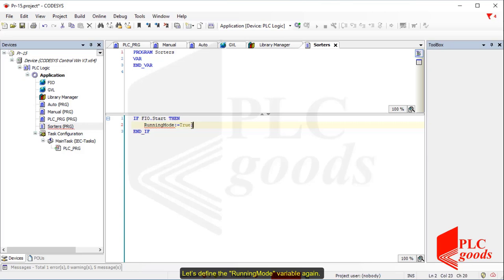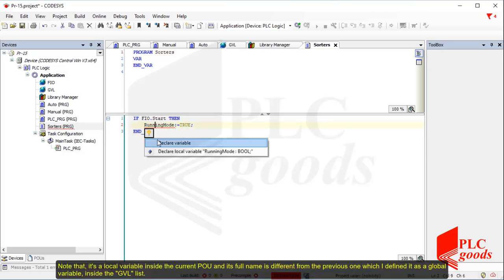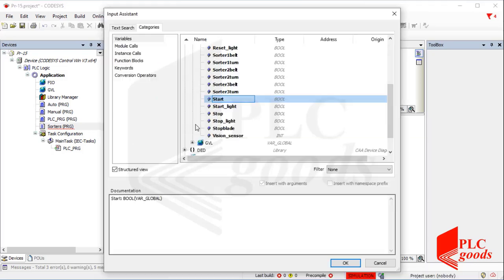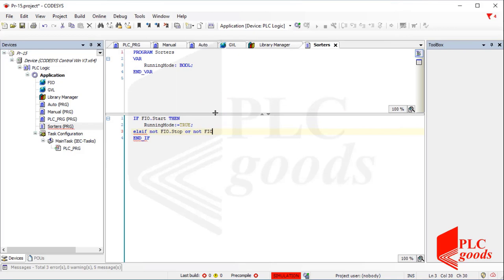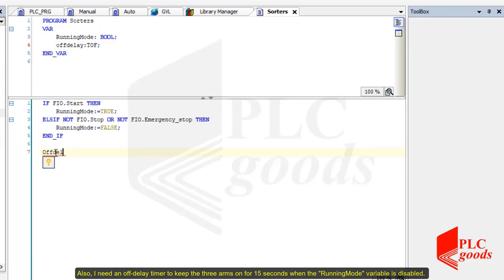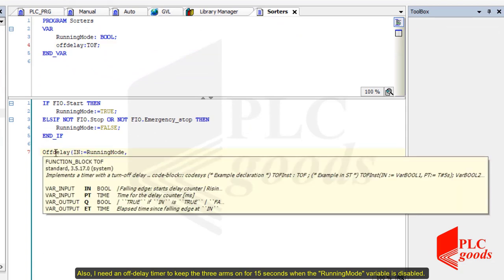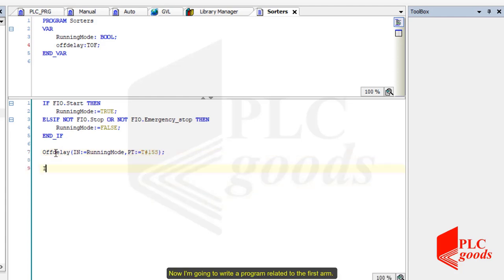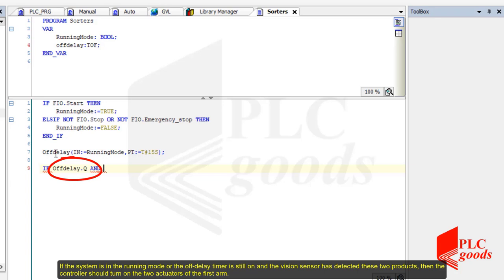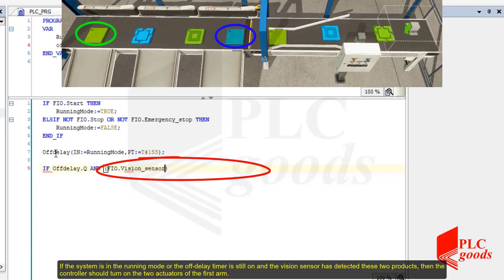Let's define the running mode variable again. Note that it's a local variable inside the current POU and its full name is different from the previous one, which I defined as a global variable inside the GVL list. Also, I need an off-delay timer to keep the three arms on for 15 seconds when the running mode variable is disabled. Now, I am going to write a program related to the first arm. If the system is in running mode, or the off-delay timer is still on, and the vision sensor has detected these two products, then the controller should turn on the two actuators of the first arm.